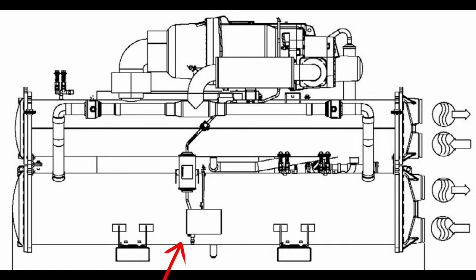So it looks like they're expecting the oil to collect here at the bottom of the condenser, and I don't see a line coming off the evaporator. Anyway, we'll circle back around to that. Coming out the discharge into the condenser, processing through the condenser, back out this bottom drop leg, and that feeds up into our economizer, which then out the economizer, this is our insulated suction line.